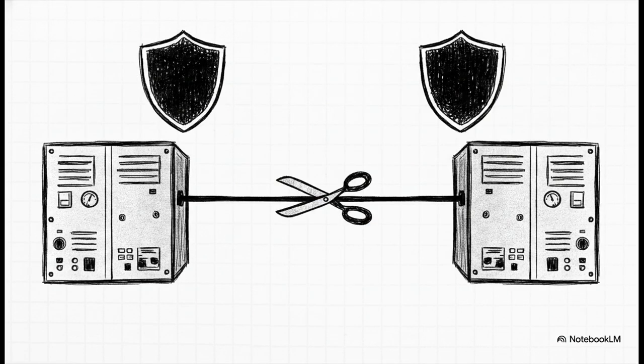So the crucial point is that the tiebreakers trip first, always. By instantly opening the tiebreakers, you effectively sever the faulty cable from both sides. But more importantly, you instantly split the entire power plant into 2 isolated, independently stable grids before a single generator gets taken offline. This maneuver buys the engineering crew critical time to isolate the exact location of the fault without completely blacking out either half of the vessel. It is quite literally a masterclass in system survivability.